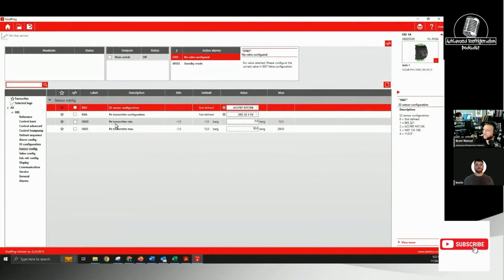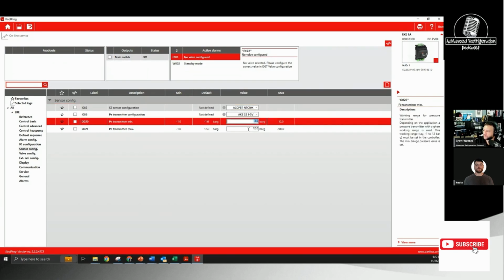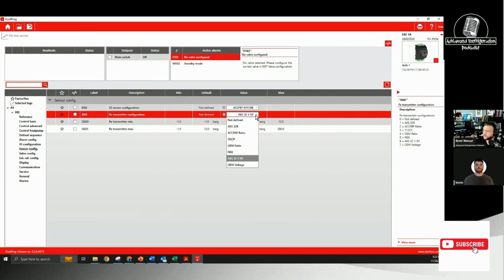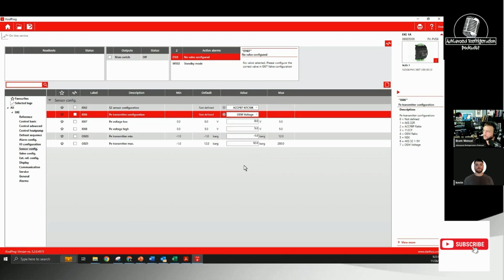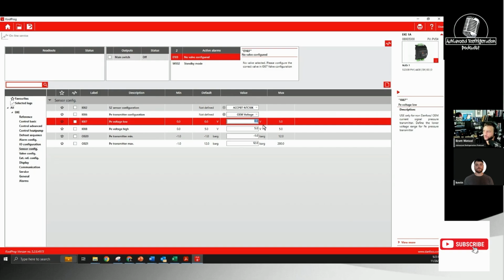Let me go back to here. PE transmitter, min and max. So this is where you'd set your range of whatever your pressure transducer is. And here's your range of pressure transducers. Here's your AKS 32R, AKS 32, 1 to 5, OEM voltage. Oh, okay, wow. So in a pinch, you could actually put whatever pressure transducer you wanted in here then.